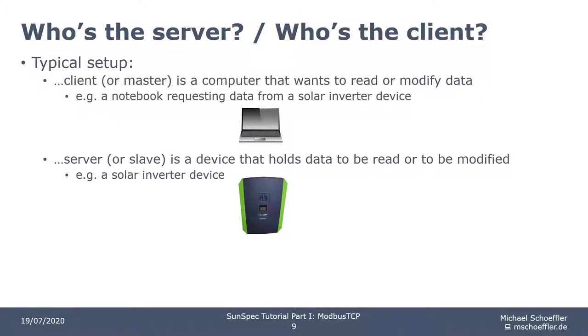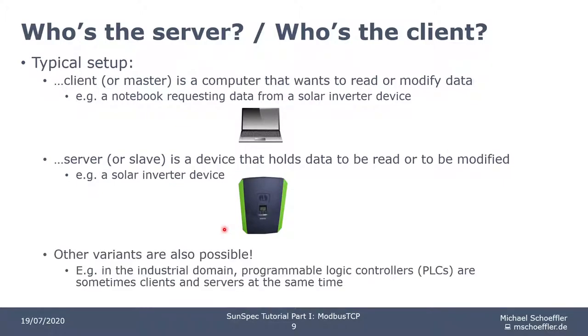But who is the server and who is the client? Here you see a typical setup. Normally, the client or master is a computer that wants to read or modify data — for example, a notebook requesting data from another device. The server or slave, on the other hand, is a device that holds data to be read or modified — for example, a solar inverter device. Keep in mind, there are also other variants possible. In the industrial domain, programmable logic controllers are sometimes clients and servers at the same time: they retrieve data from other Modbus servers, aggregate it, and then make the aggregated data available to other systems by opening their own Modbus server.